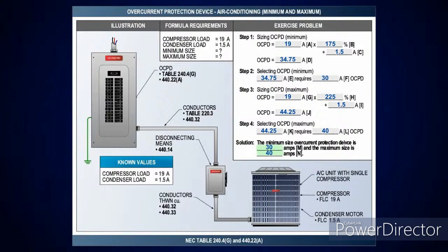So, nice. If I look at this, I've got a compressor here that's 19 amps and a condenser at 1.5. So you have to take the largest motor here at 175% per 440.22A. So I take 19 amps at 175%, add the condenser at 1.5, and that gives me 34.75 amps. I said you drop down, because when you read that section, what does it say? A protective device having a rated setting not exceeding 175%. If you can't exceed it, that means you do what? Drop down. This is going to be a minimum starting size. So that would give you a 30 amp overcurrent protection device.